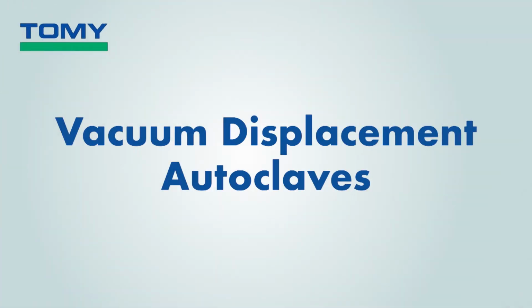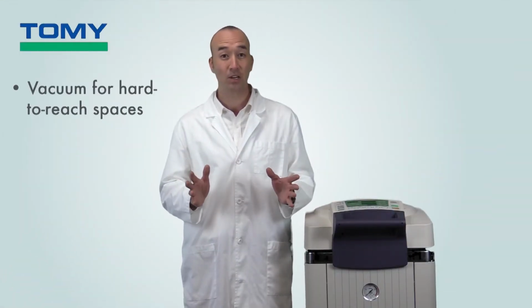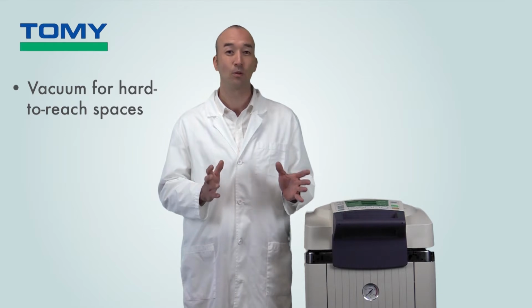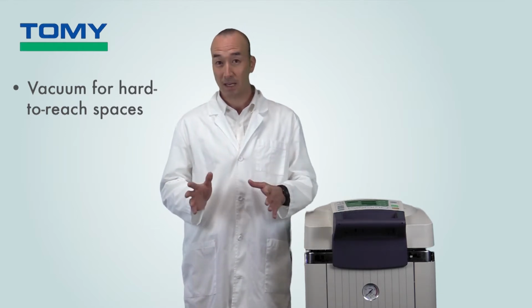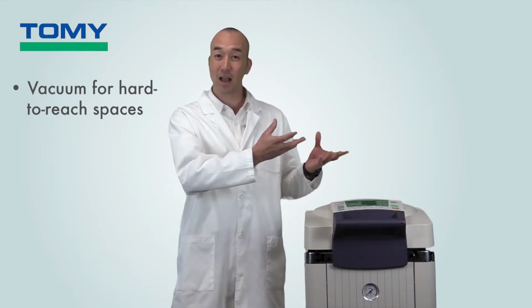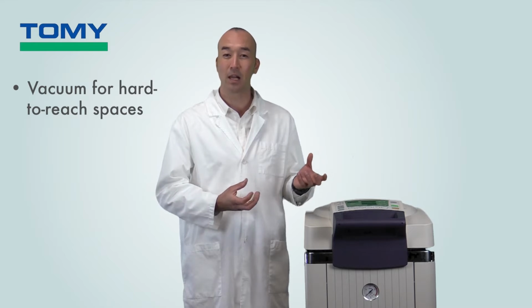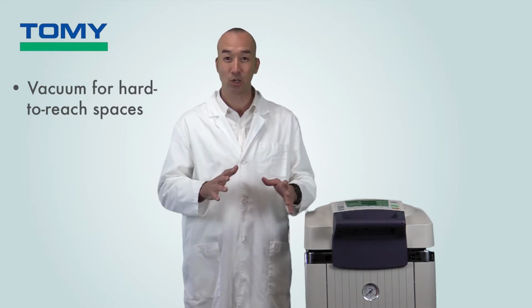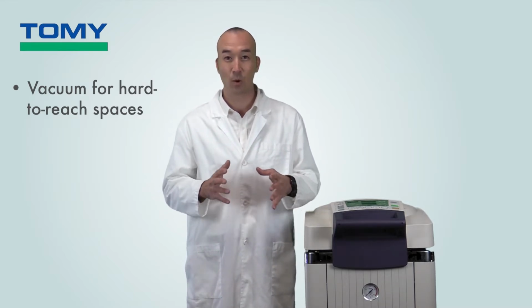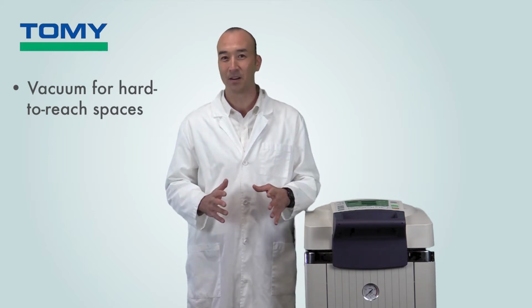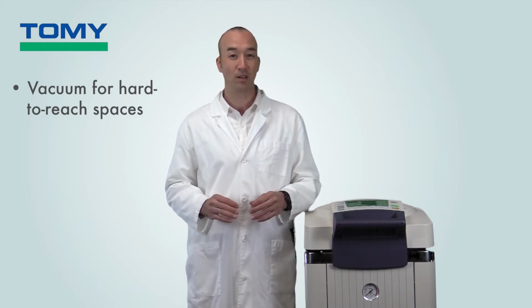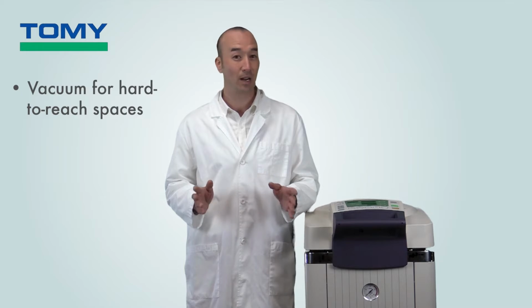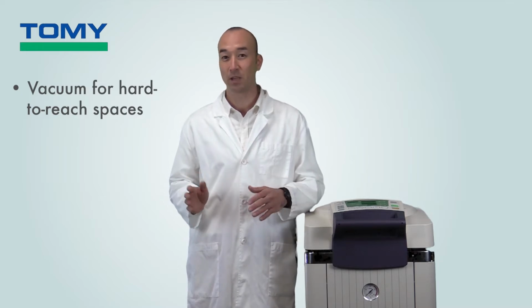Vacuum or vacuum-induced autoclaves, also known as pre-vac autoclaves, allow for sterilization in harder to reach places through a vacuum mechanism. In these autoclaves, a vacuum pump evacuates the ambient air within, allowing high temperature steam to penetrate and sterilize areas that would normally be occupied by ambient air. Through this vacuum replacement function, these autoclaves can sterilize certain items with hard to reach areas within.